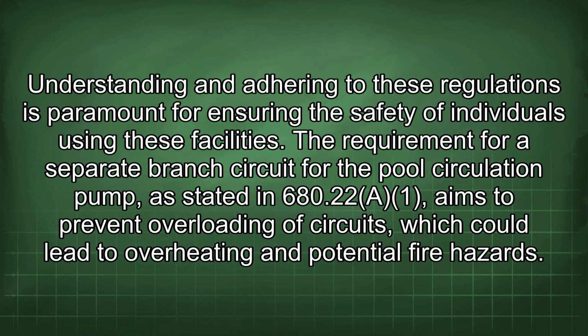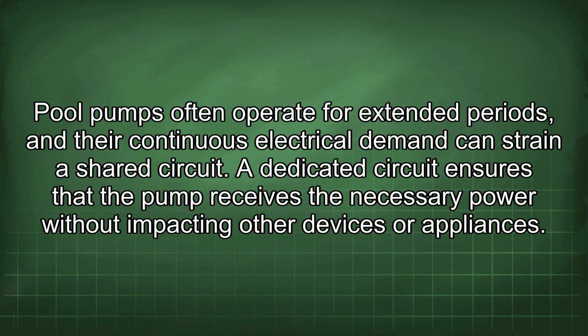The requirement for a separate branch circuit for the pool circulation pump, as stated in 680.22(A), aims to prevent overloading of circuits, which could lead to overheating and potential fire hazards. Pool pumps often operate for extended periods, and their continuous electrical demand can strain a shared circuit. A dedicated circuit ensures that the pump receives the necessary power without impacting other devices or appliances.